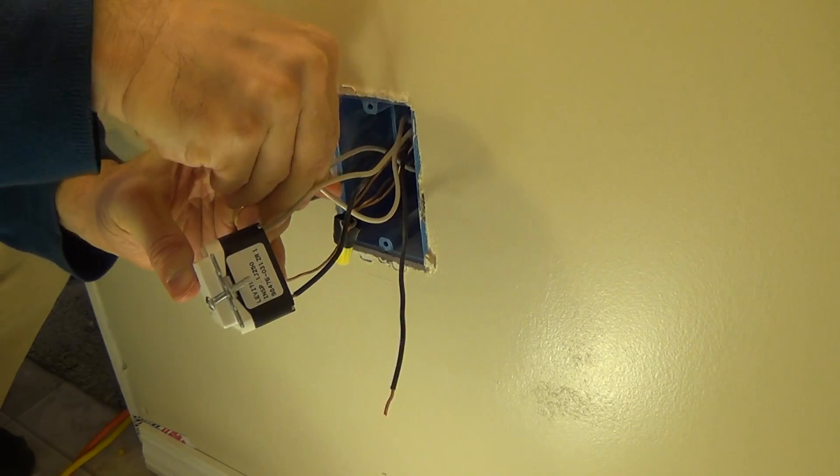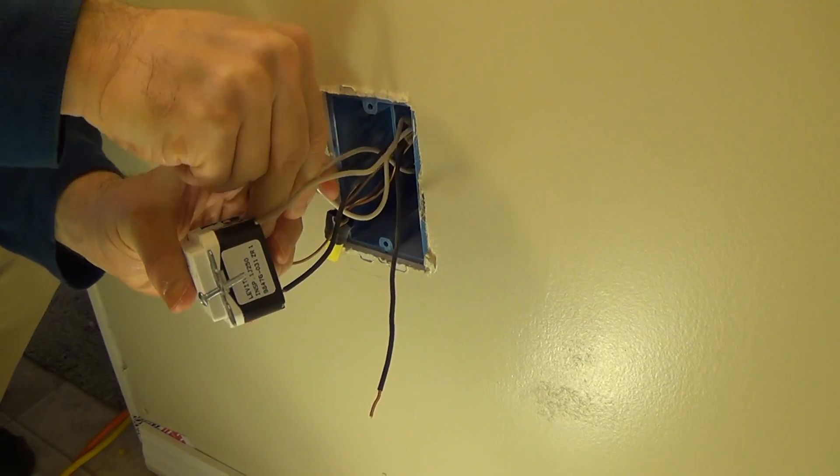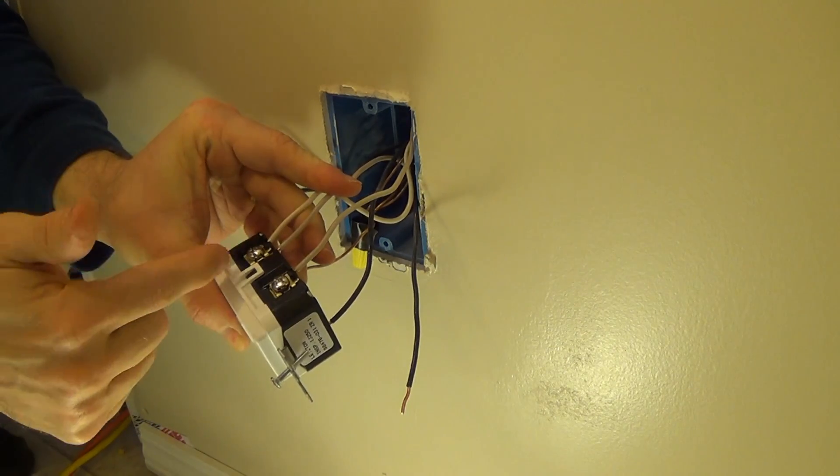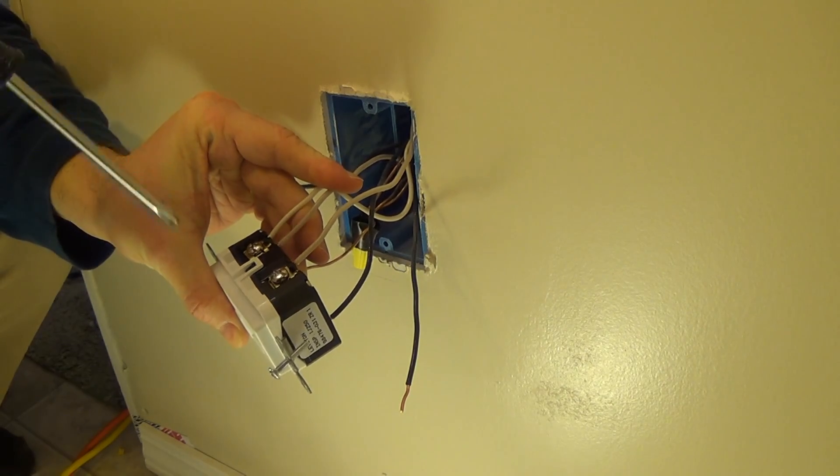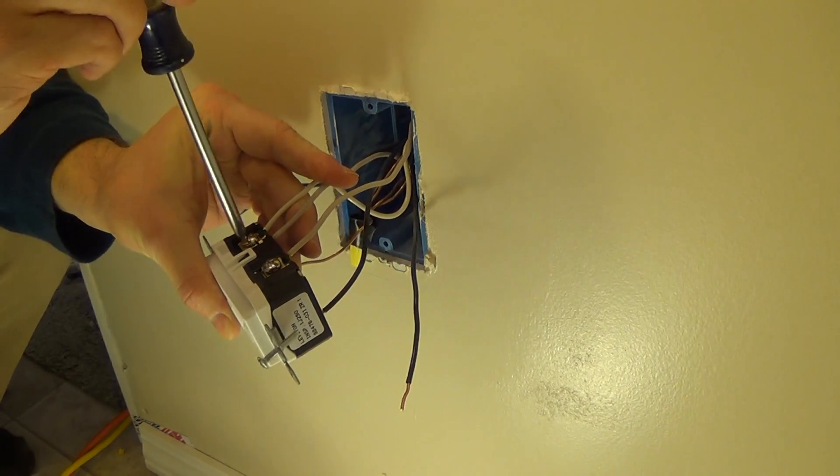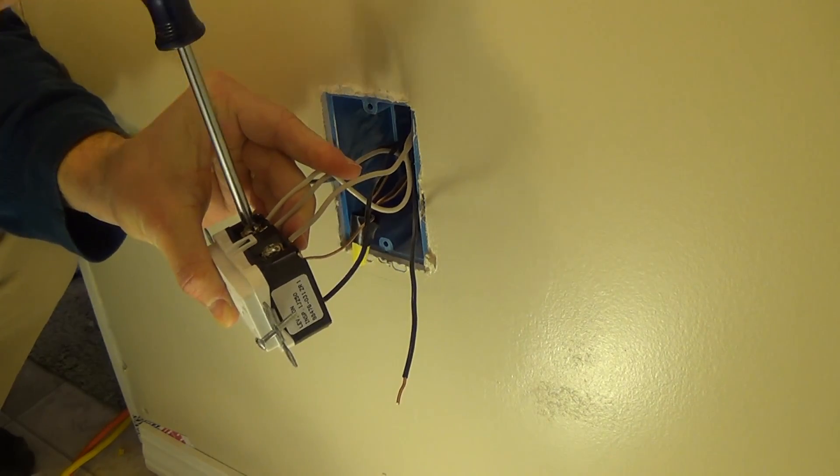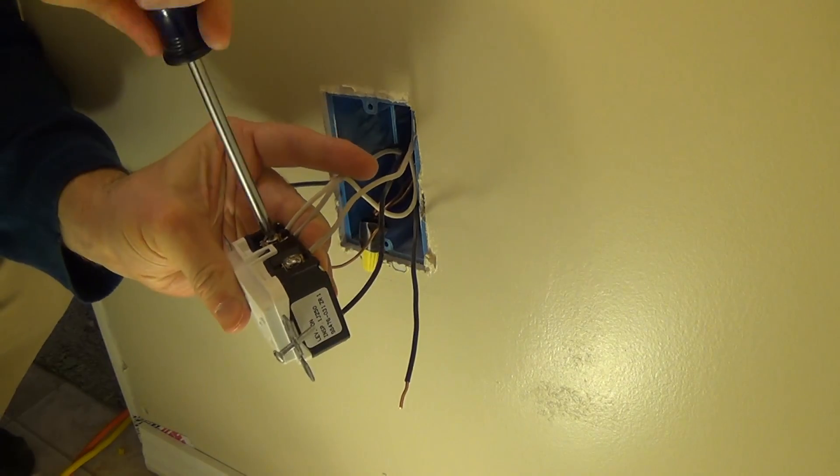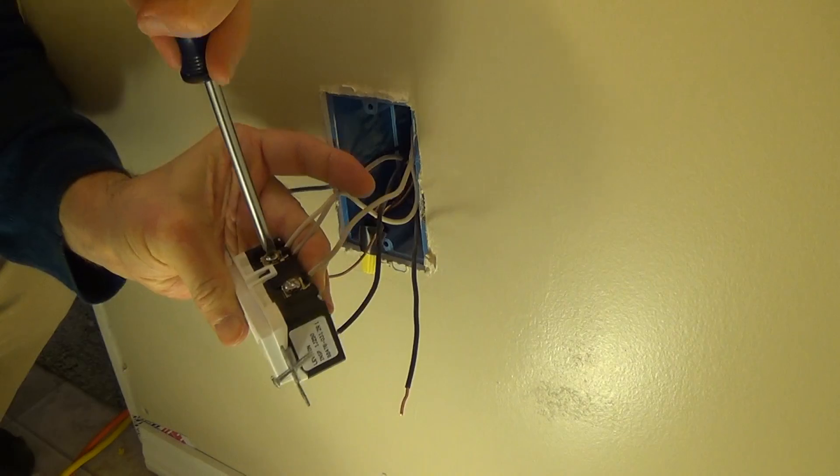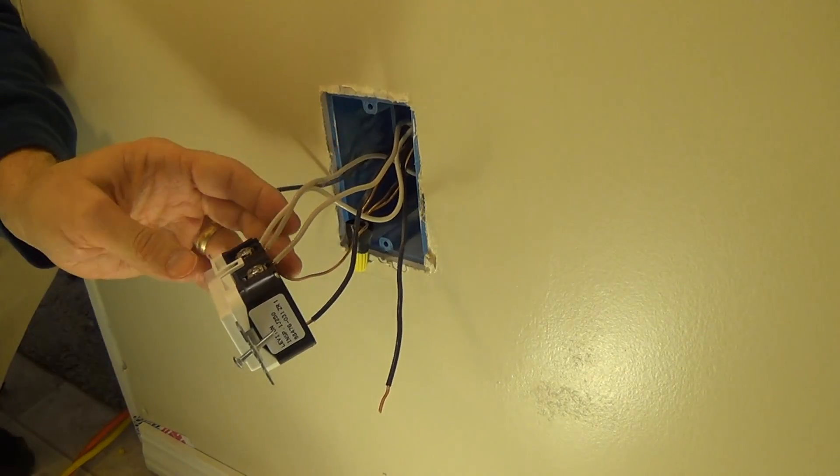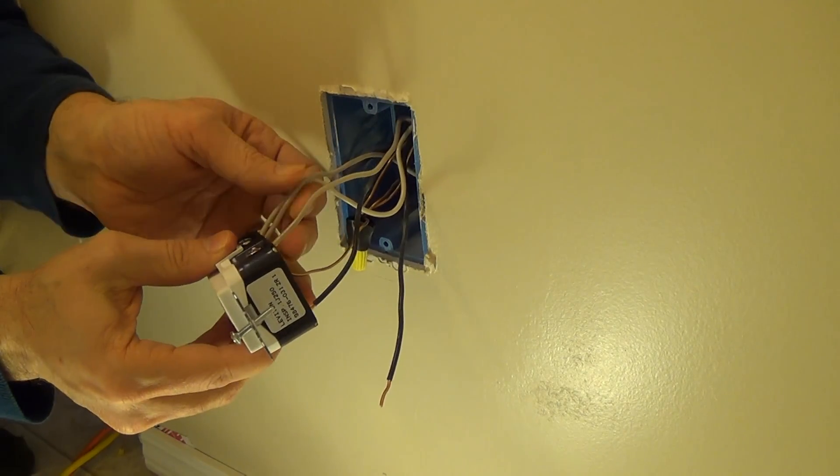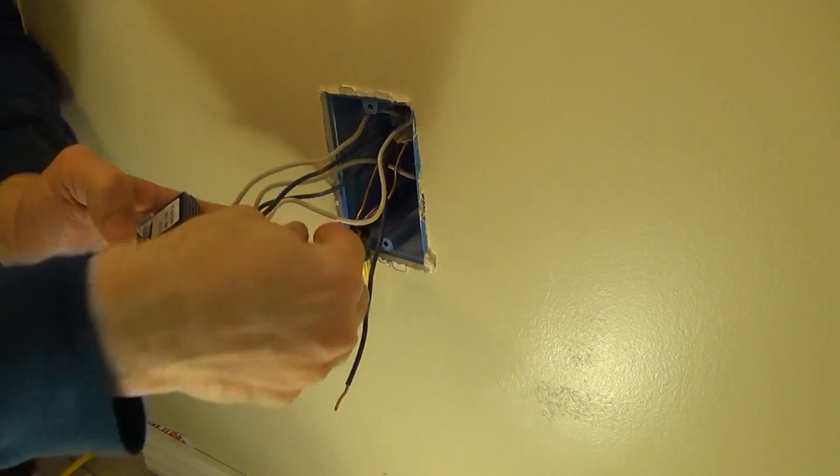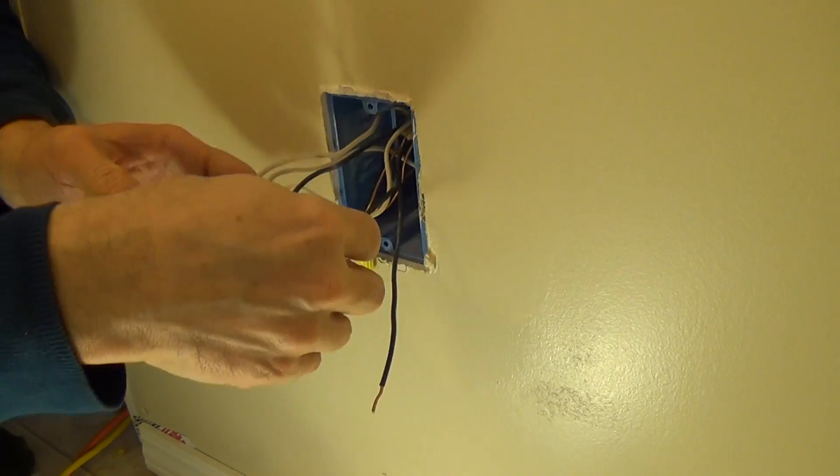You have to loosen the terminal, stick one there, now grab the other white wire, put it on the opposite side. And these little terminal clamps are very handy because you could stick in two wires in one little terminal clamp and they'd secure them very well. Where if you actually try to secure them in with the screw nut, it'd be very insecure.